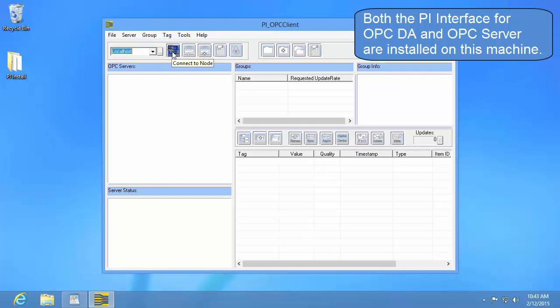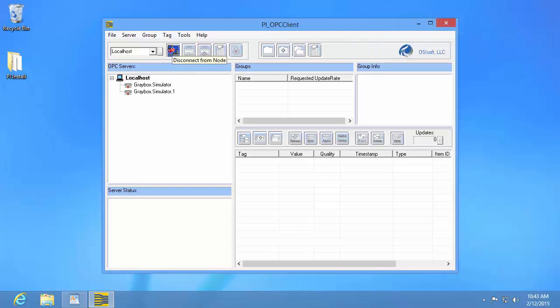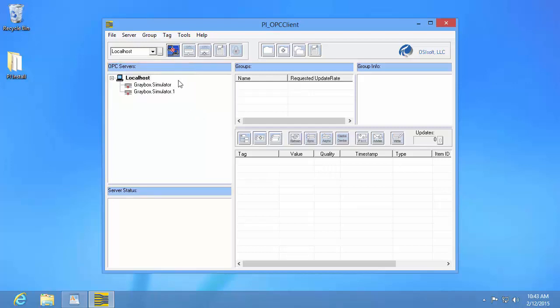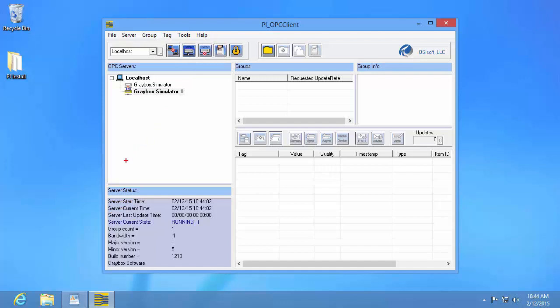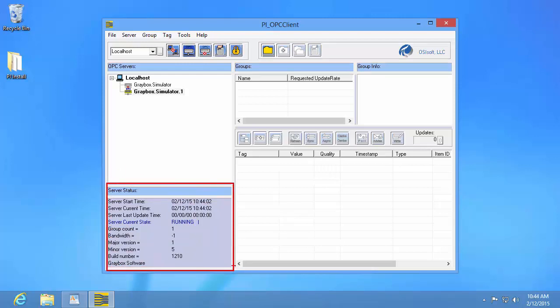Next, I'm going to click on the 'Connect to Node' button, which is here. This is going to populate the OPC servers field, which lists all the OPC servers that the PI OPC client was able to find on the node. Then I can choose which OPC server I want to connect to and press the 'Connect to OPC Server' button. This will populate the server status field, which confirms that we were successfully able to connect. You can also see the server current state, which is 'Running' — this is what you want to see if your OPC server is healthy.